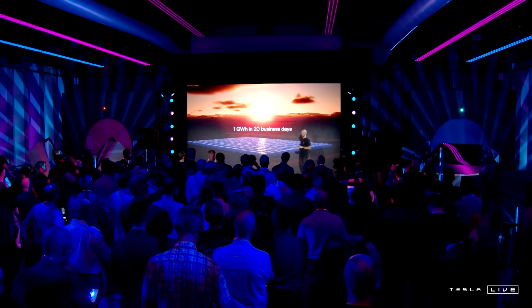One example is how we use simulation. We like to bring our customers, and sometimes utilities and grid operators, into a room with our engineers, sometimes months before the megapacks are even delivered to the site. We can take your actual hardware and software controls—the actual software you'll be using on site—simulate the grid at the exact point where you'll be connecting, and run a bunch of simulations, control scenarios, and grid scenarios to see if it's going to work like we thought. It's essentially a peek into the future to see if the project is going to work. Our customers love it—it's a great opportunity to sort out bugs in the software, and it gives confidence that when the megapacks are connected to the grid, it is going to work.